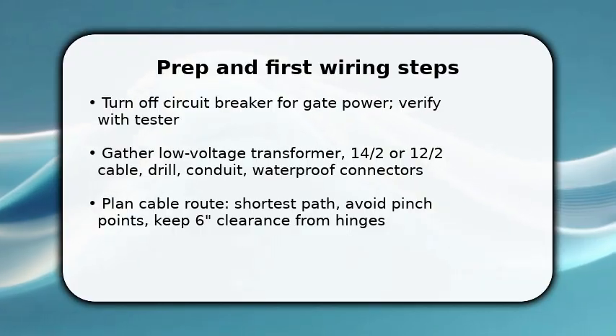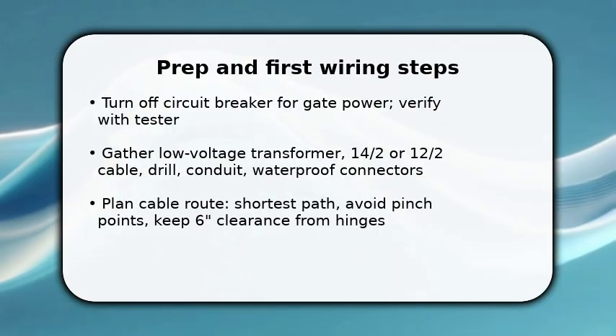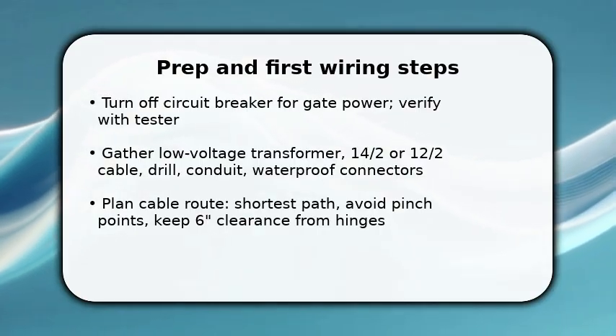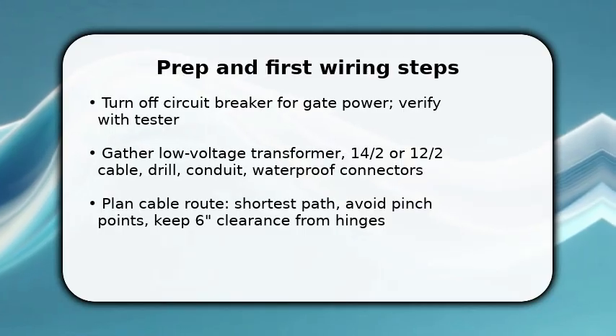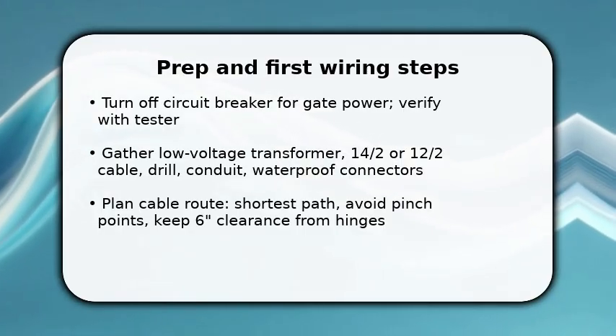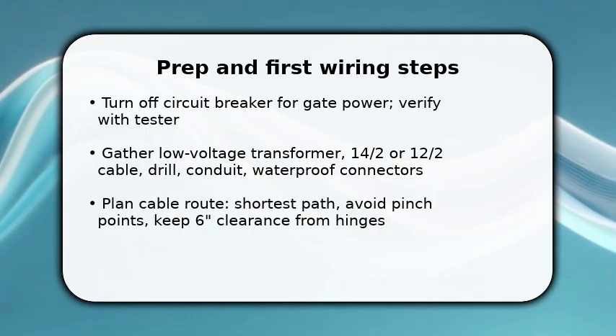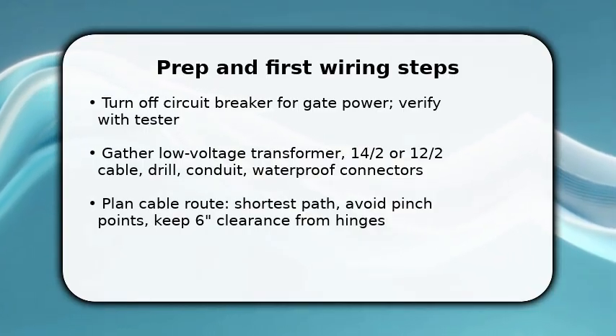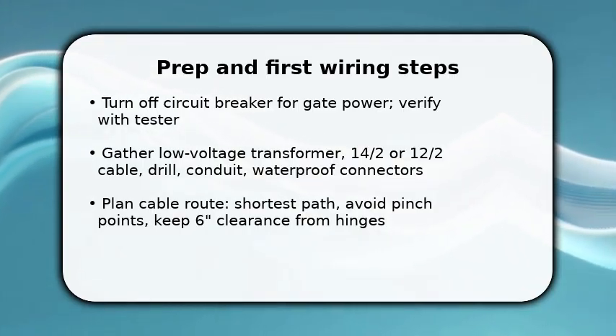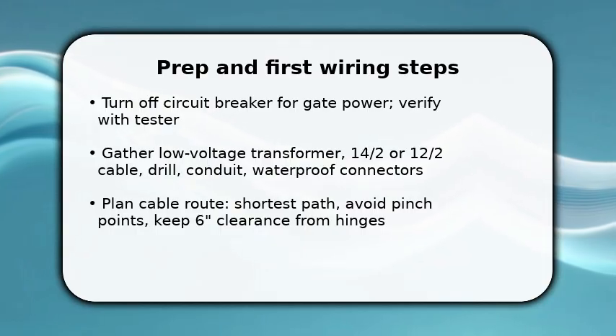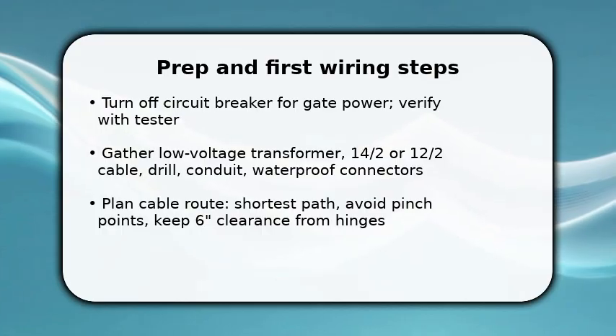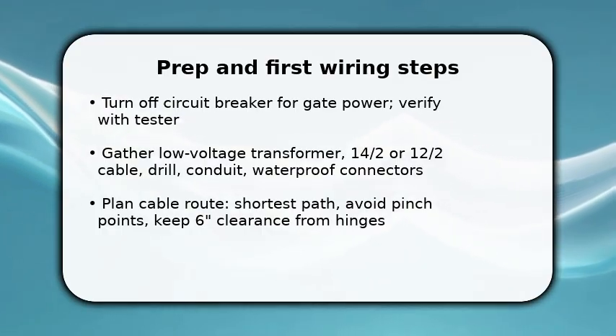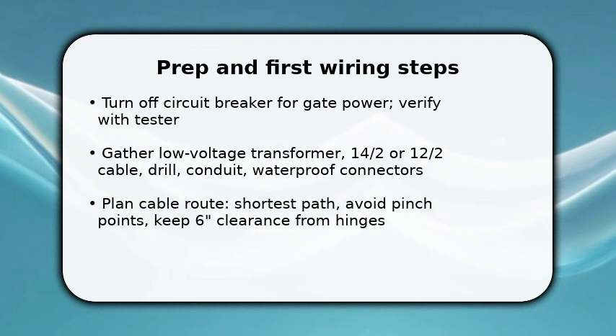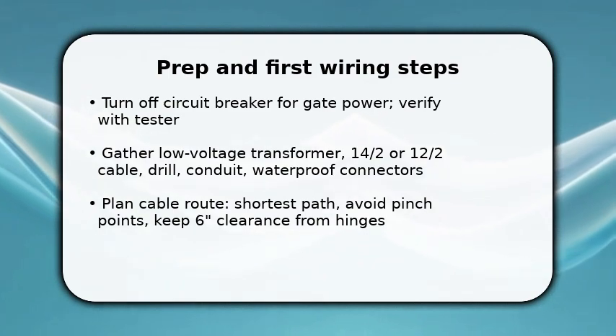You start by cutting power and confirming dead wires with a tester. Safety first. Next, mount the low-voltage transformer near the breaker or outside GFCI-protected box so voltage drop is minimal. Once done, route the appropriate cable from transformer to gate using conduit where exposed. This protects the wire from mechanical damage and weather. Make sure to secure the conduit every 3-4 ft and leave a small service loop at the gate for movement.